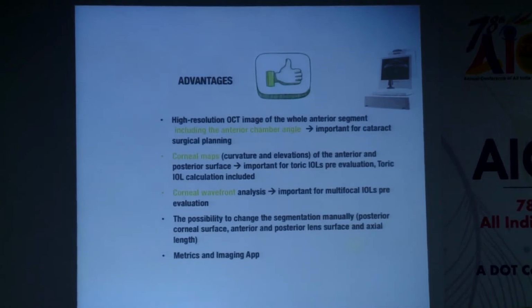The principle, as I said, is based on swept source OCT. The wavelength is 1300 nanometers. Digital axial resolution is less than 10 micron, and the scan depth is 14 millimeters. So the advantages of Anterion are the higher resolution that it has, along with imaging the anterior chamber angle, which is very important for the planning in surgical cases.